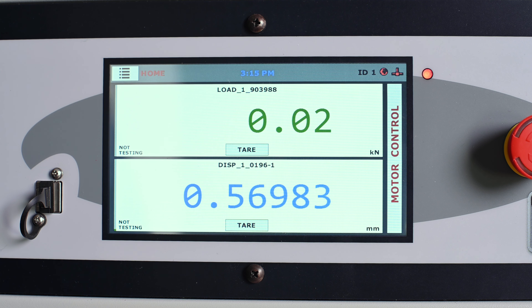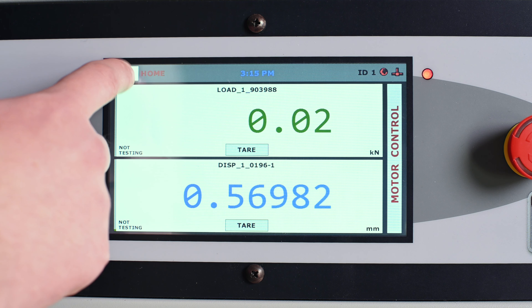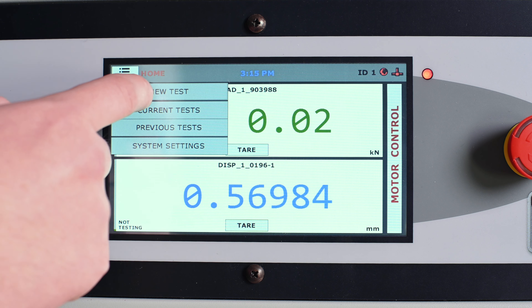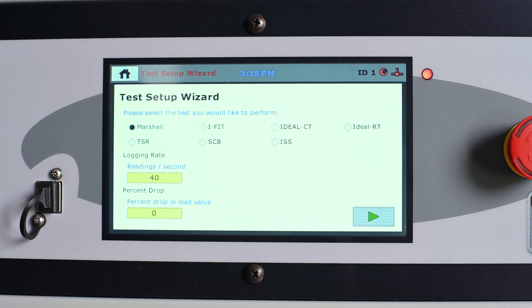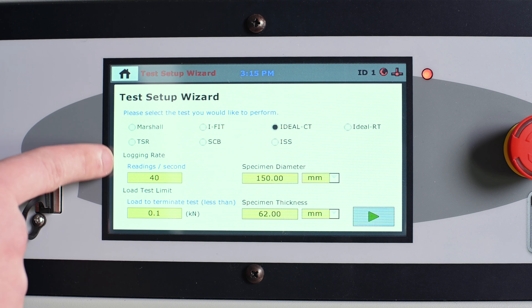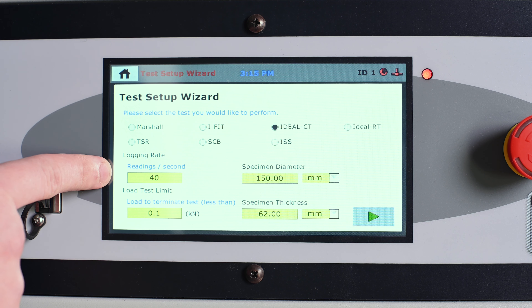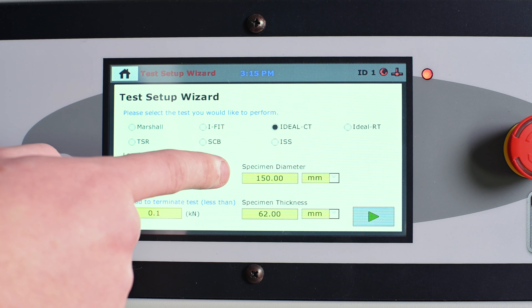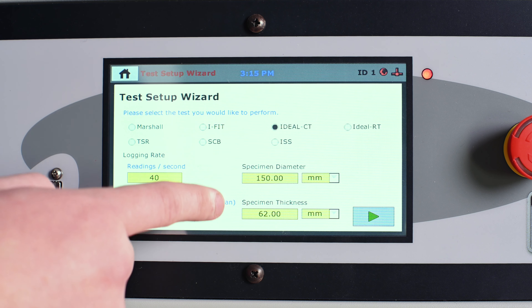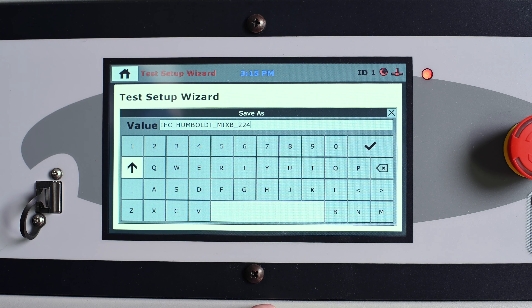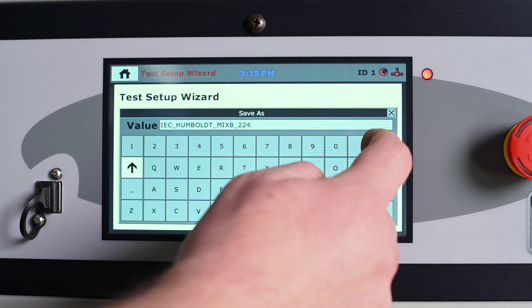This easy-to-operate load frame allows you to simply choose the type of test you want to run in the test setup wizard. The load frame chooses the standard parameters, which for IDEAL CT would be the logging rate, the load test limit, and the specimen diameter and thickness. All of these parameters can be changed manually if needed.